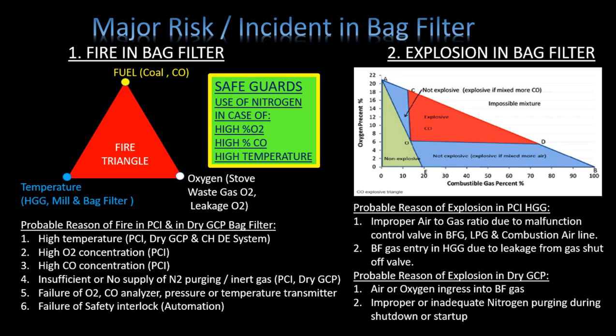Explosion in bag filter: probable reasons of explosion in PCI-HGG include improper air-to-gas ratio due to a malfunctioning control valve in the BFG or LPG combustion airline, and BF gas entry into the HGG due to leakage from the gas shut-off valve. Probable reasons of explosion in dry GCP include air or oxygen ingress into BF gas, and improper or inadequate nitrogen purging during shutdown or startup.